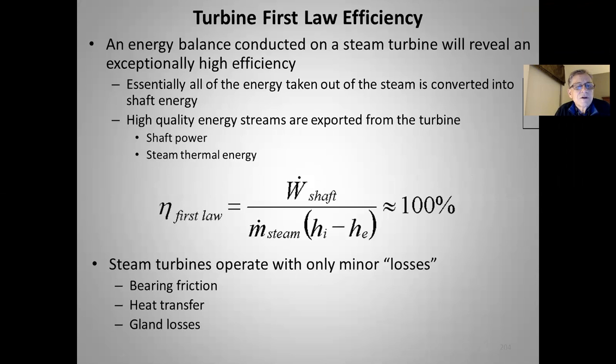The steam exiting a turbine still contains a lot of energy. The first law efficiency — shaft work divided by mass flow rate times the enthalpy difference — is not of great interest because it always comes out very, very close to 100%. Steam turbines operate with only minor losses: a small amount of bearing friction, heat transfer, and gland steam leaks along labyrinth seals, but unless something's wrong, it's a powerfully small amount.